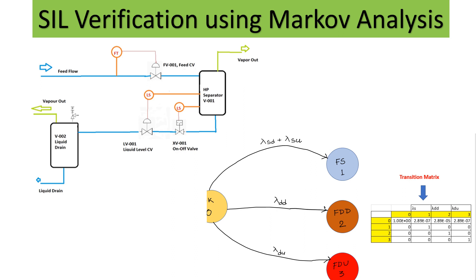From the last two videos we have been discussing about SIL verification using Markov analysis. We discussed states, state matrix, transition matrix, and calculated the PFD average value for one-out-of-one and one-out-of-two configurations. In this lecture I am going to discuss how to do complete SIL verification of a safety instrumented function using Markov analysis, and how to get the total PFD average value of the loop.